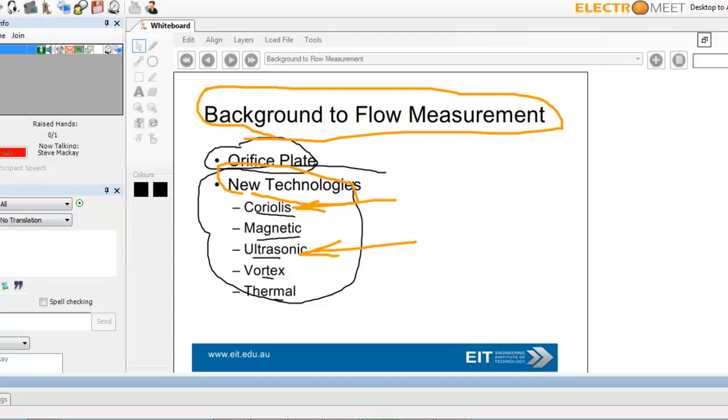So, Coriolis is quite simple. In some respects, difficult to grasp when you look at the diagrams, but basically, you've got two vibrating tubes. The fluid accelerates through the tubes, which reaches the point of maximum vibration, and then when it decelerates, the fluid decelerates as it leaves the point of maximum vibration. And you have a twisting motion in the tubes, and the degree of twisting is proportional to the fluid's mass flow.